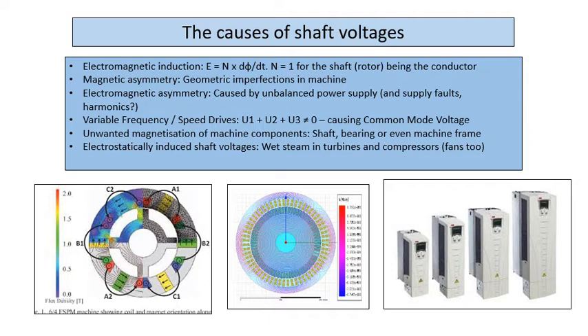The main cause of shaft voltages. Now this is 50 hertz. It applies to high frequency as well. And Stian introduced it, but you treat your shaft as a single turn conductor. And if you have flux linking that turn, you'll have a voltage across it. So if you look at a 4-pole machine, it's got that field that rotates around it.